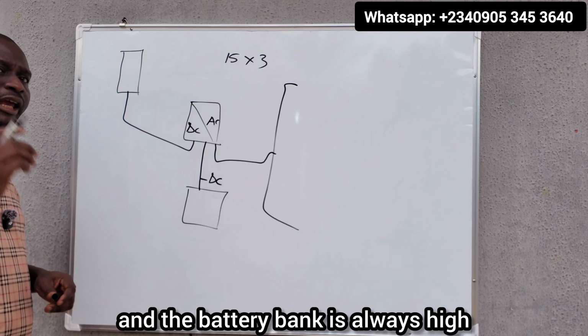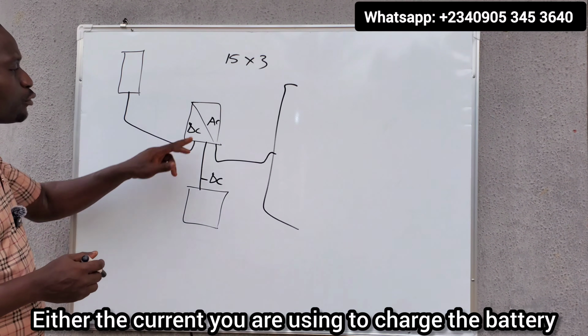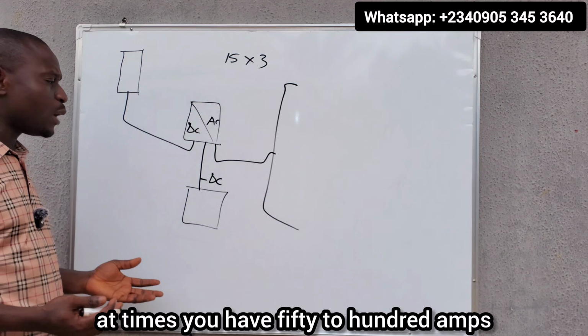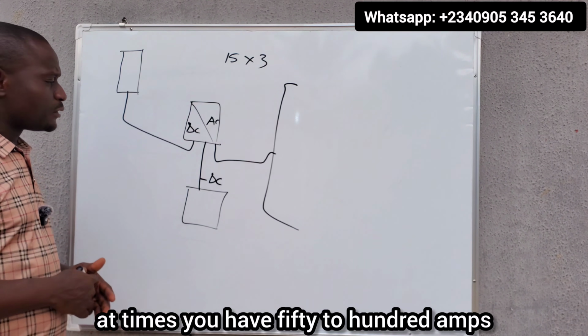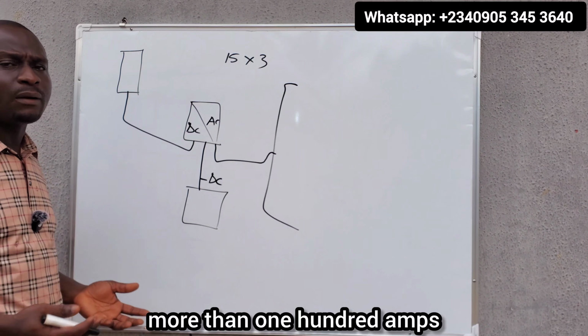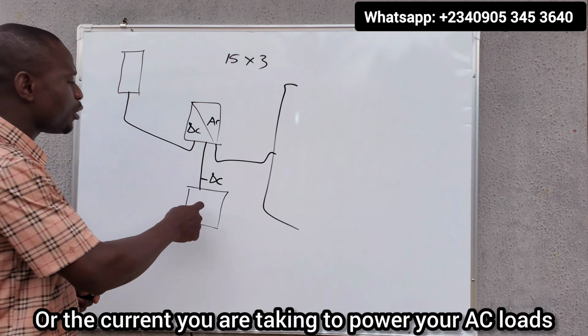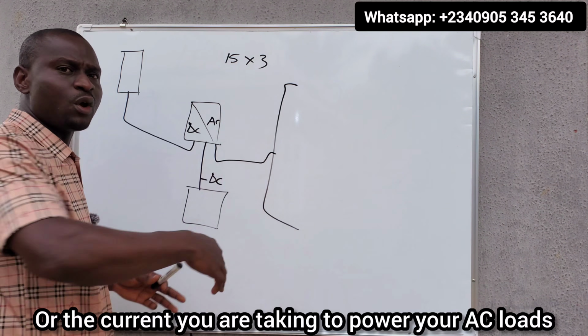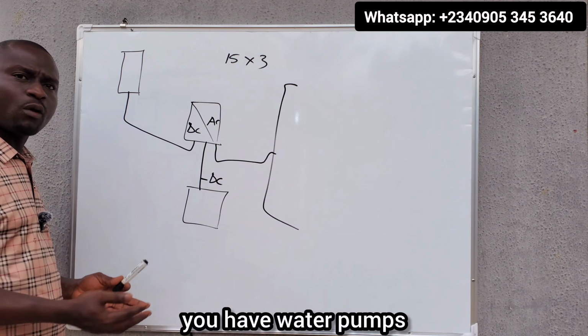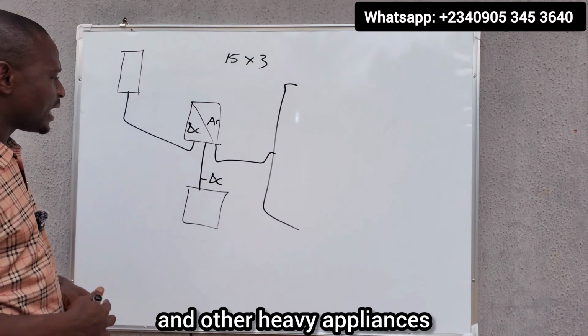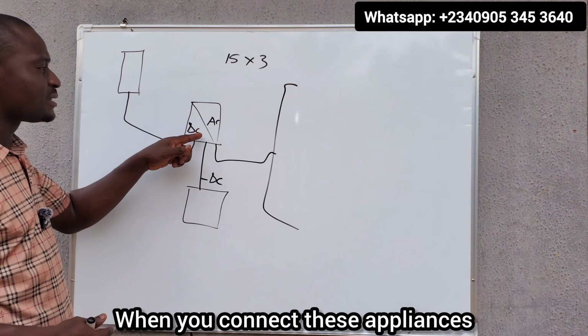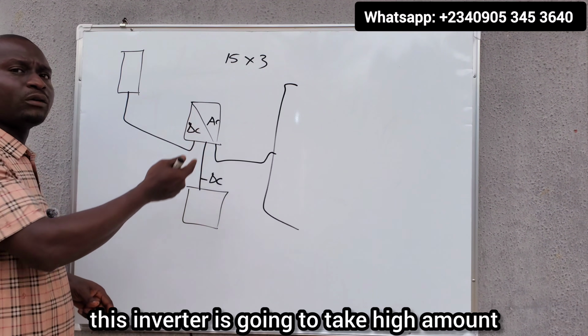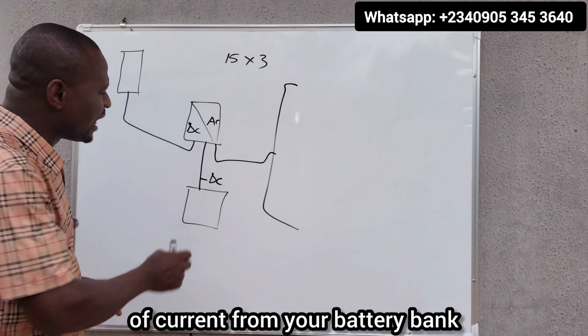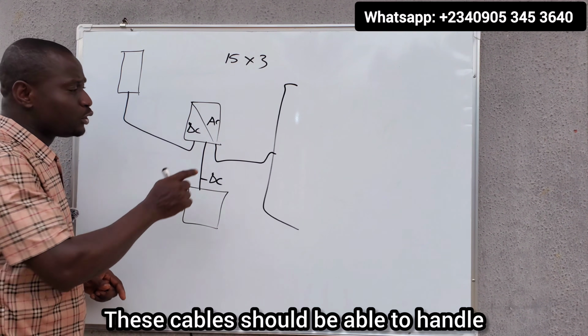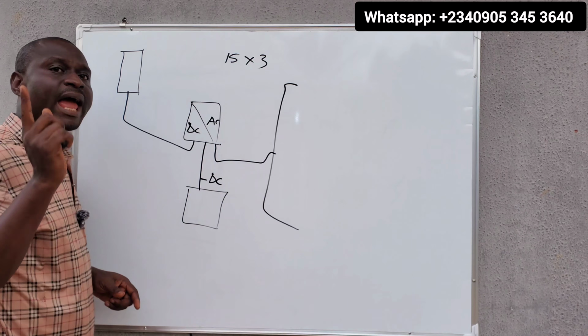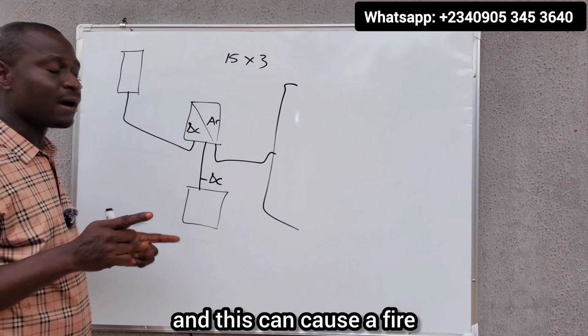From the hybrid inverter to the battery, here we have high DC cables because the current between the inverter and the battery bank is always high. Either the current you are using to charge the battery, at times you have 50 to 100 amps, in some cases more than 100 amps, or the current you are taking to power your AC loads, where you have air conditioners, water pumps, and other heavy appliances. When you connect these appliances, this inverter is going to take a high amount of current from your battery bank. These cables should be able to handle that amount of current, else they can melt and this can cause a fire.